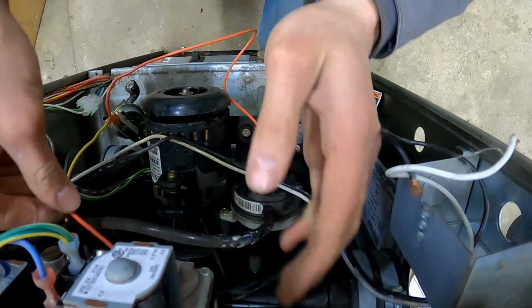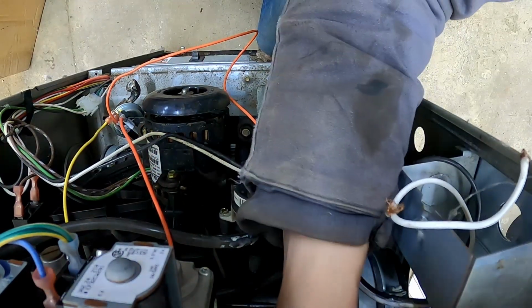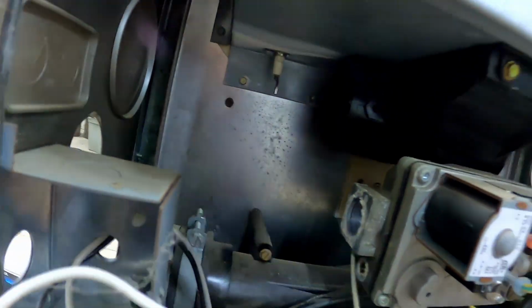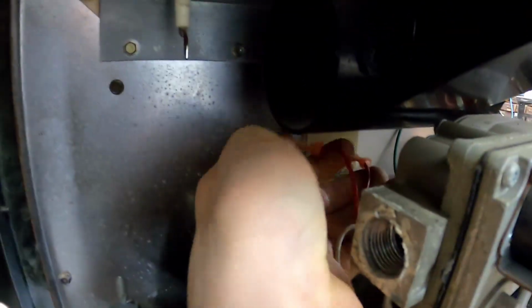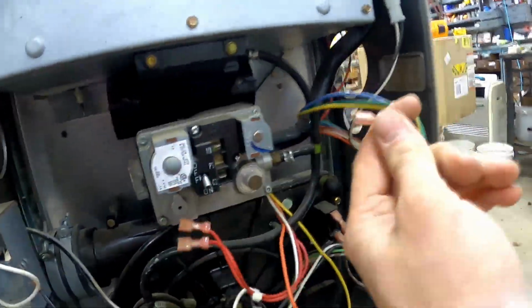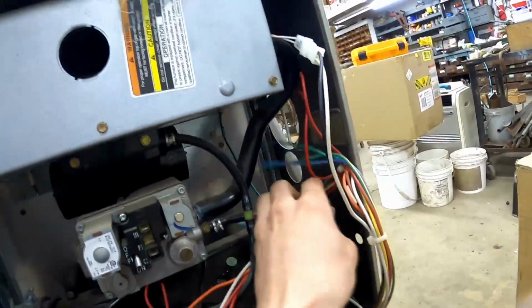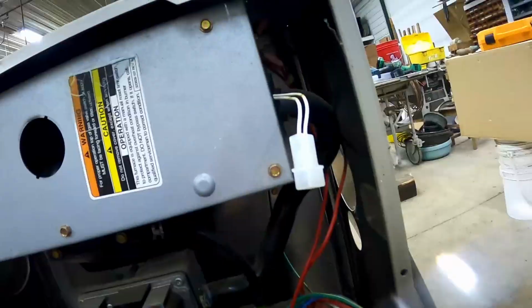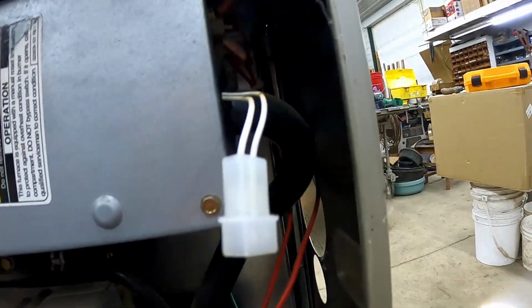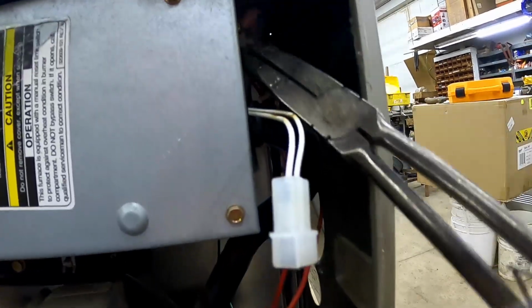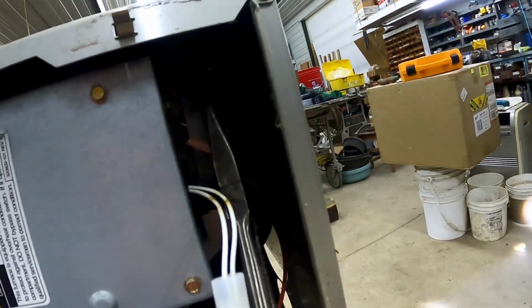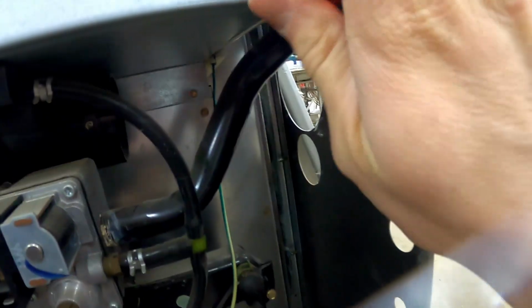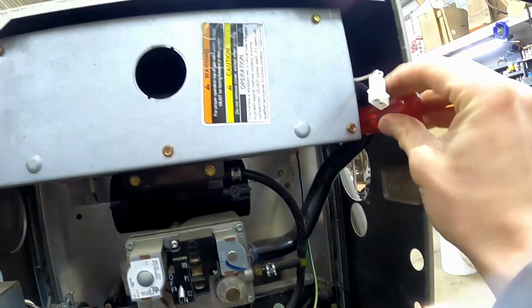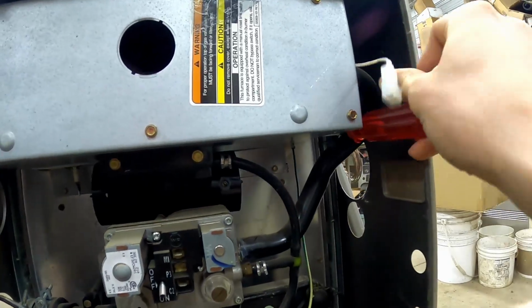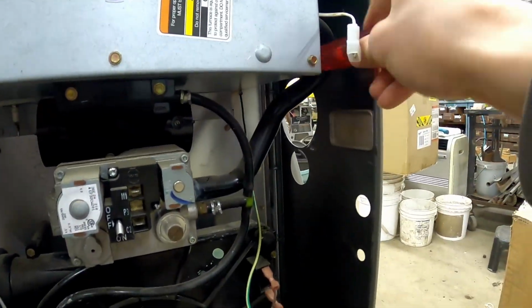Next we're going to pull this off of the pressure switch and continue removing wiring up in here. So we've got flame sensor. These two red ones go to the high limit. Gas valve. Igniter. Rollout switch right up in there. It's usually kind of hard to get to, so it's nice to have a tool for that. Ground screw. Since these units use flame rectification as their flame sensor, you have to have really good grounding on the burner assembly.